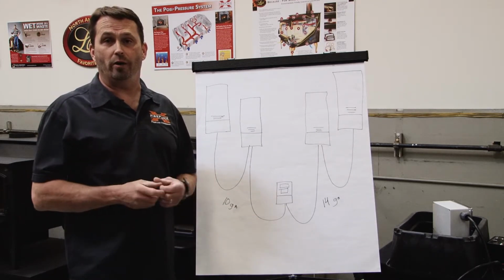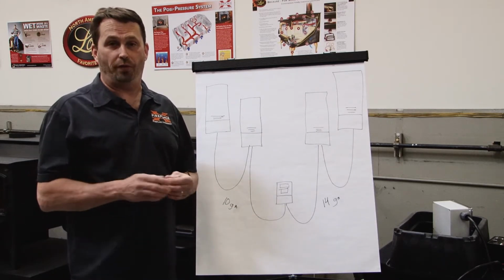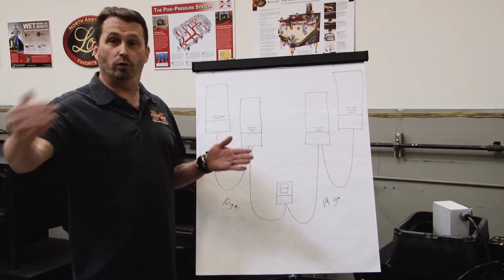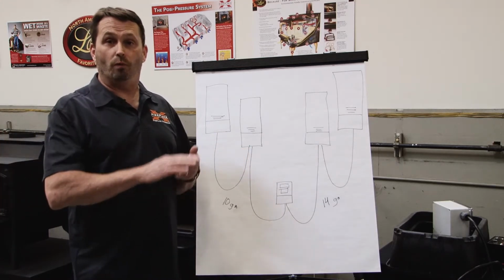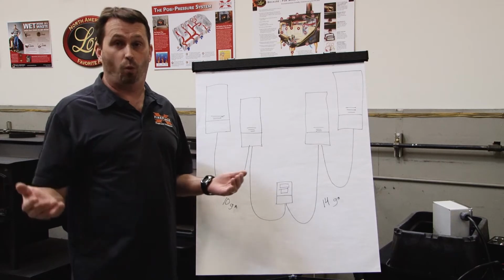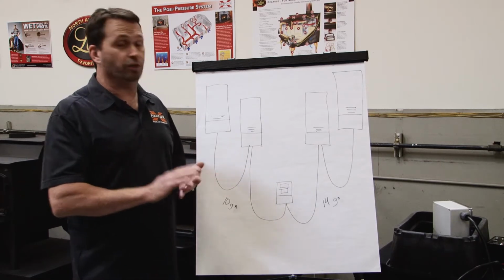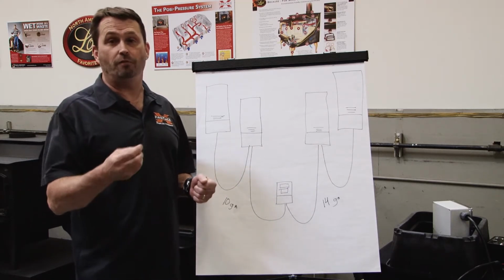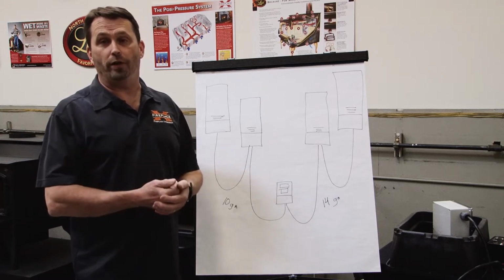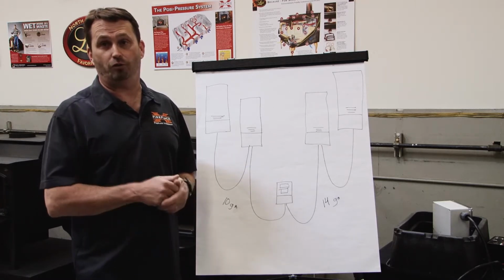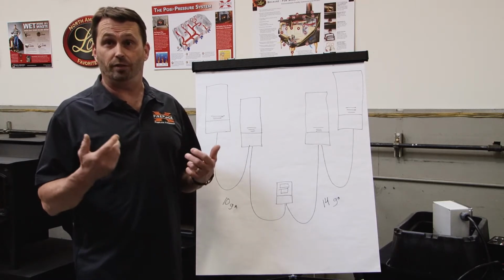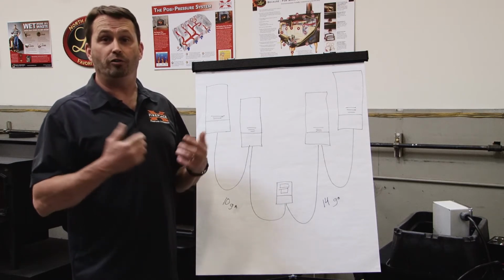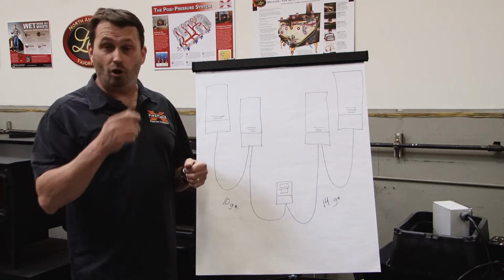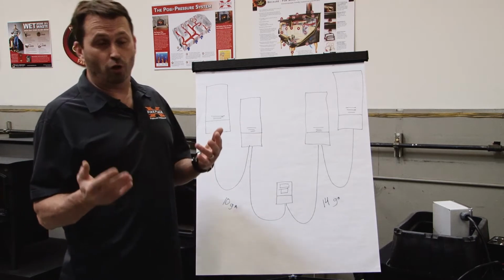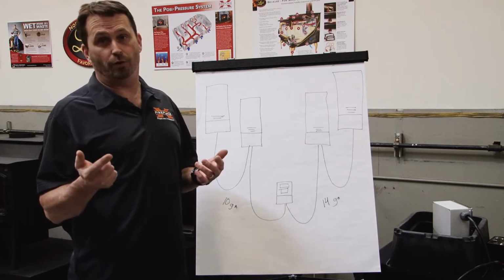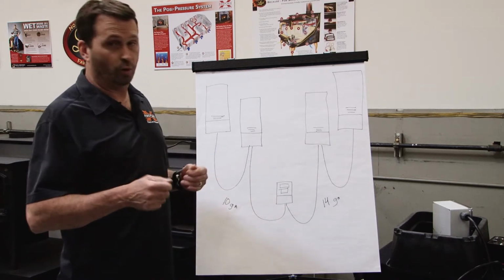Low voltage wiring, you have to be careful with that because the longer the wire run you have, the more voltage will drop over the course of the wire run. So it's critical that the torch receives enough voltage to operate the components, and specifically the hot surface igniter needs the critical level of voltage to get hot enough to ignite the gas. So following along on our chart, there are 2 ways that you can wire the torches from the transformer.